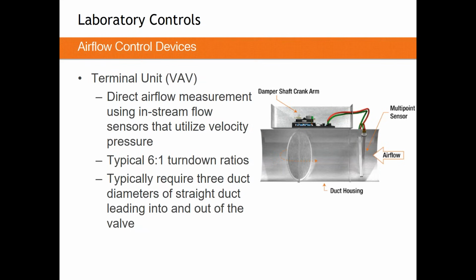The upside to a VAV box is they're extremely low cost and they use almost no pressure to measure that airflow. So you're going to see a VAV box measure in the 100th to a 10th of an inch kind of range, which is extremely low pressure. The great part of that is they'll work in retrofit applications, they work in low pressure systems, but again, they're not the most accurate and don't have the highest turn down. I mentioned 6 to 1 here. More commonly, you're going to see these as 3 to 4 to 1 turn down ratio devices. So if you're looking at an operating room that needs to go from 25 air changes down to 6 or 10, this device will really struggle to do that accurately. The other devices we're going to talk about can achieve that fairly easily.